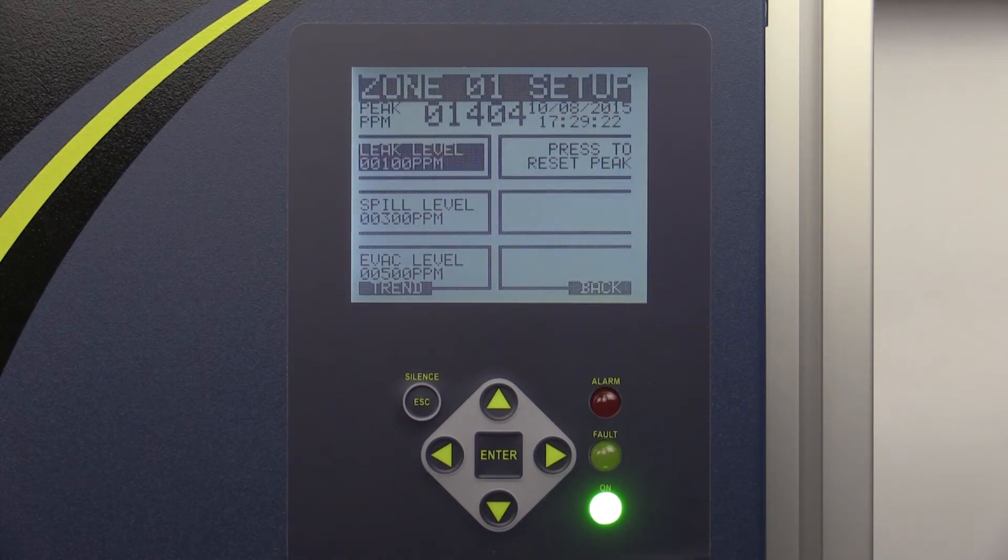If a single splitter was used for a specific zone, the leak, spill, and evacuation levels should be halved from their desired values in order to account for dilution of the contaminated air caused by the mixture of samples from two separate sample points. If a triple splitter was used, the leak, spill, and evacuation levels should be reduced to one-third of their desired values for the same reason.